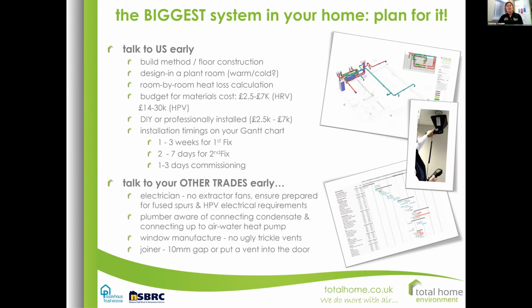Please do talk to your other trades early as well. Prepare your electrician: he doesn't have to quote you for extractor fans, etc., but he does need to quote for getting those fused spurs to where the units are, and any electrical control cables and things like that. Make sure your plumber is aware of connecting up the condensate and connecting up to the air to water heat pump. That particular unit is all pre-plumbed, but there is obviously still some connection to do.